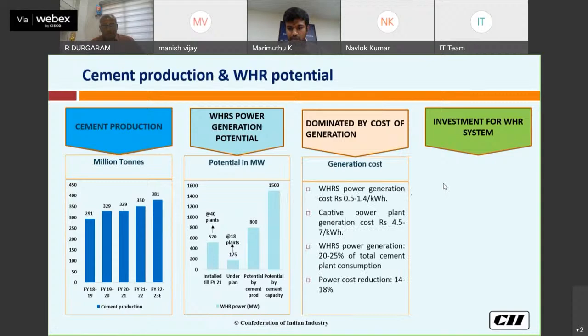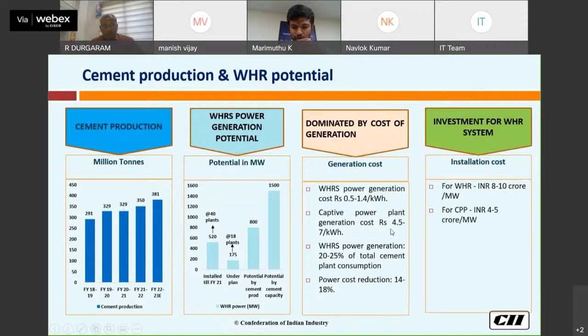Why we have to go for WHRB is because of the operating cost. For a captive power plant now, due to the coal crisis, the power cost is more than 6 rupees. Generally we get between 4.5 to 7. But in WHRS, the operating cost will be 0.5 to 1.4. With WHRS, we can manage 20 to 25% of total cement plant consumption, and it also reduces the power cost by 14 to 18%. So out of 100%, 20 to 25% we can cover with this WHRS production.